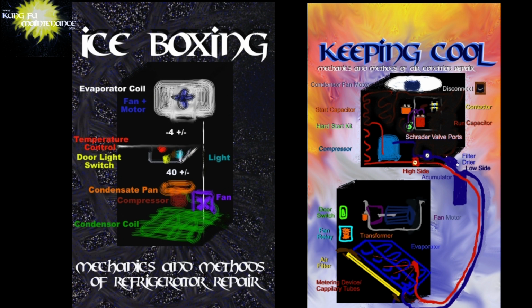If you get too much ice, or you don't have enough airflow and you get a buildup of ice, then things aren't going to work. Years ago, you had to manually defrost the freezers once in a while. Now things have been engineered to use a defrost timer and a defrost cycle to keep that ice melted and to create what's called the frost-free refrigerator. Walk-in coolers use defrost timers that run through cycles to make sure that ice doesn't form on the evaporator coil, doesn't create airflow blockage, and keeps things cold.